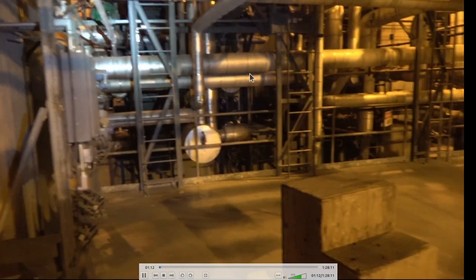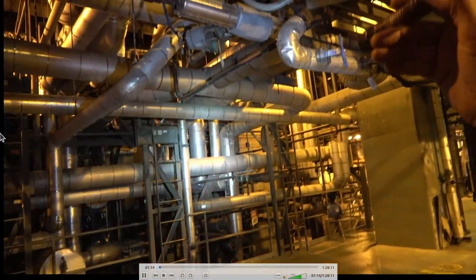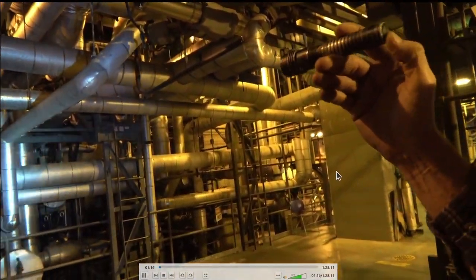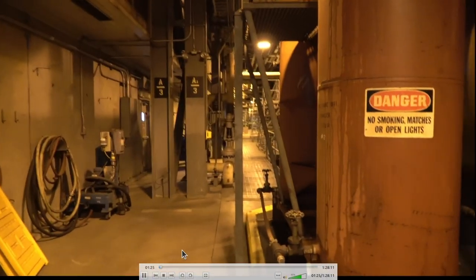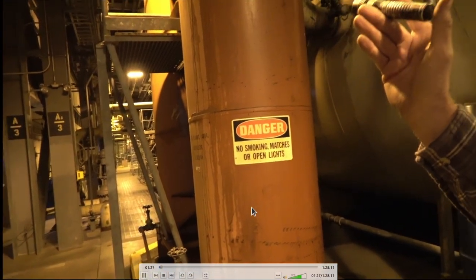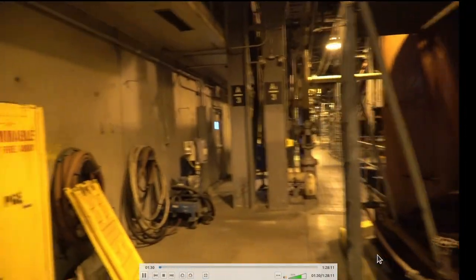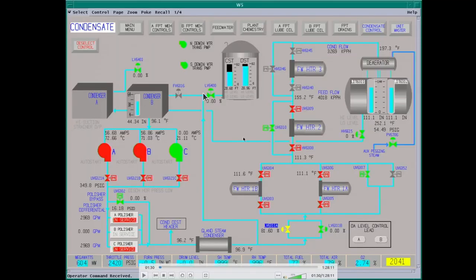Over here are the condensate pumps, and this is the front of the surface condenser. These are all the drain lines coming back to the surface condenser, used for startup and various conditions. This is the lube oil cooler — there are two of them. This is the condensate system. We have two surface condensers, one for each low-pressure turbine. The condensate goes to the condensate pumps, then to the polishers — resin beds with cation and anion resin, which cleans up any impurities in the water.